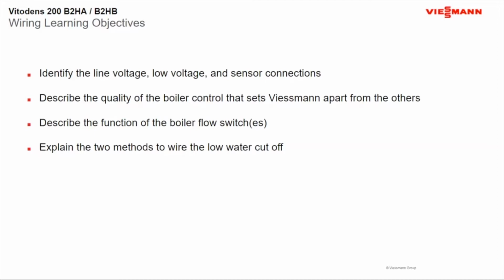And we'll talk about how to wire in your low water cutoff. And right prior to that, your flow switches actually have been approved to be your low water cutoff. So if you needed like a piece of paper to show your inspectors, usually the reps have that on file for you, and they can send that out to you. But in some states, they still require, like I'm pretty sure New York City requires a low water cutoff. So we'll go over that as well, where to wire that. And if you're doing multi-boilers, we actually have a multi-boiler low water cutoff box that you can put all your low water cutoffs to one box. So if you haven't seen that yet, we actually have that as well.